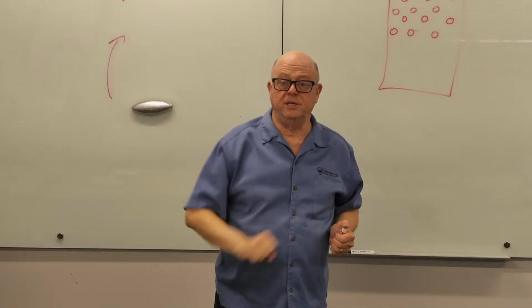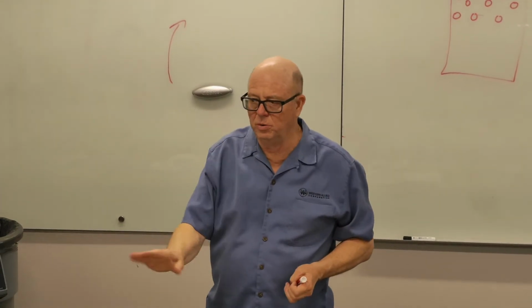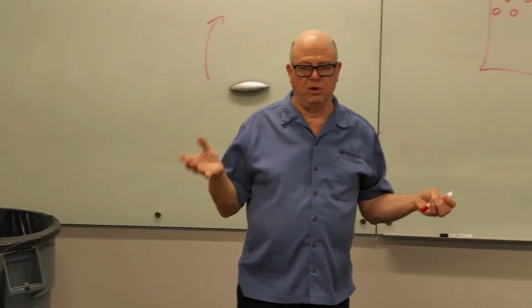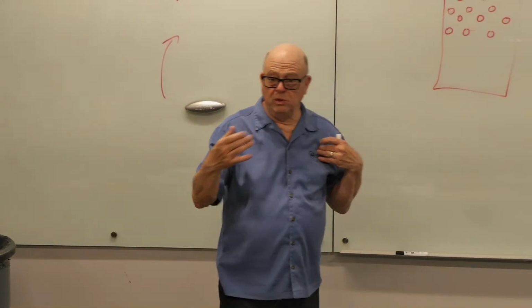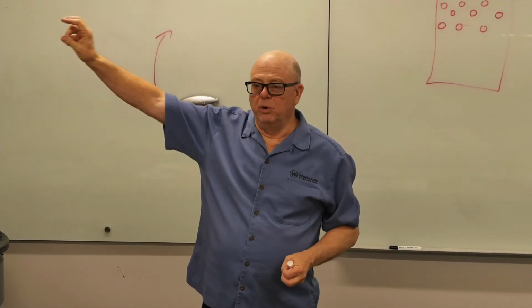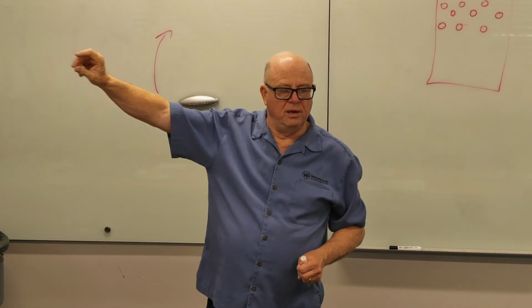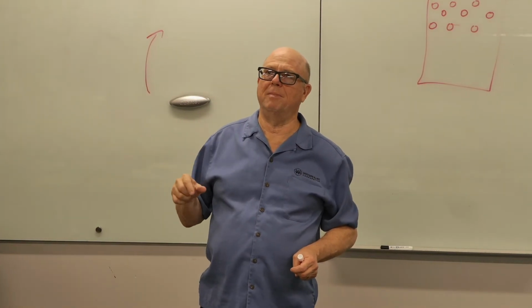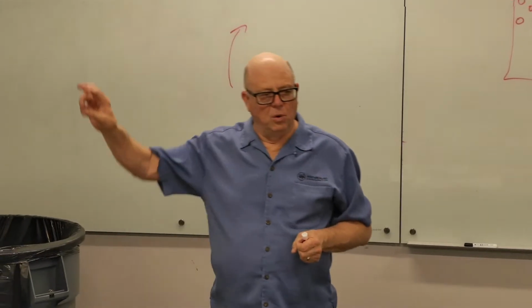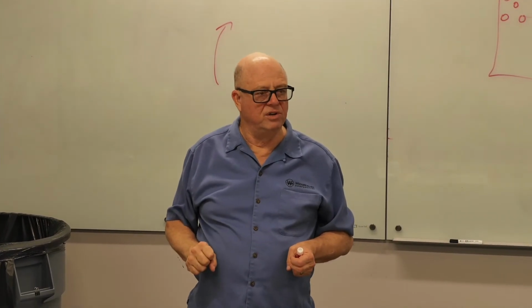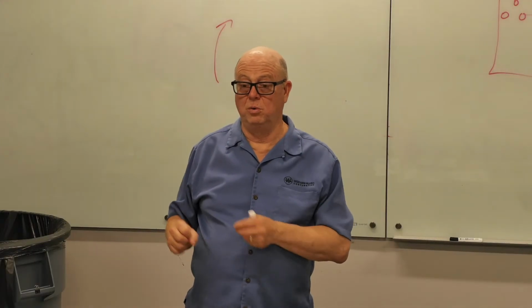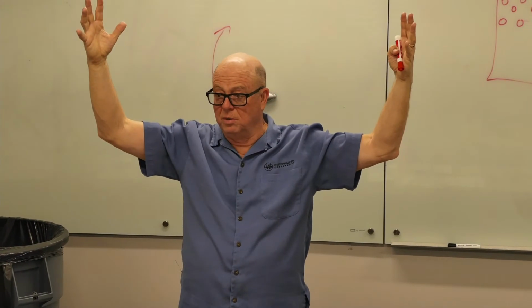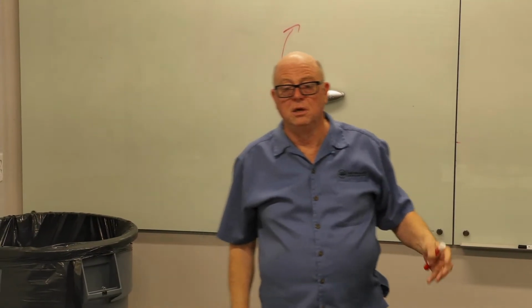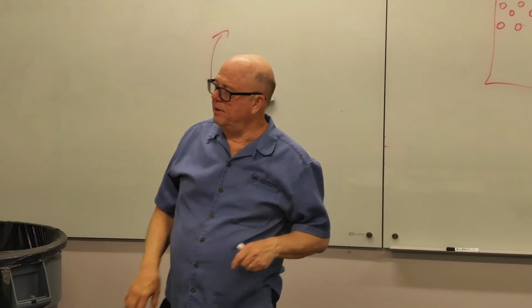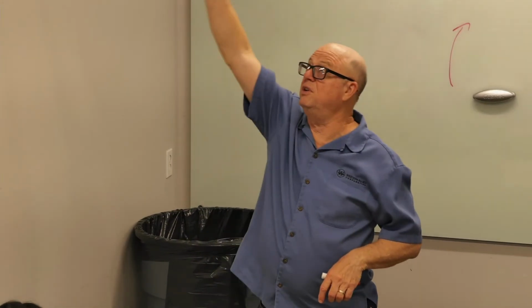Like I say, now that we're using LEDs, they put off very little heat. I won't say no heat, they put off some heat, but a lot less than fluorescent bulbs would have. And when I was in my 20s, we weren't using a magnetic ballast, we were using, or did I get that right? The old style ballast, now I don't even remember what they were called. But the old style ballasts, they put off a shitload of heat. In fact, you would bump whatever the wattage of the lights were by 25% just to cover the ballast. Long story short, today, if it's 72 in the stat on the wall, it's probably 74 at the ceiling, it's probably 75 in the room.